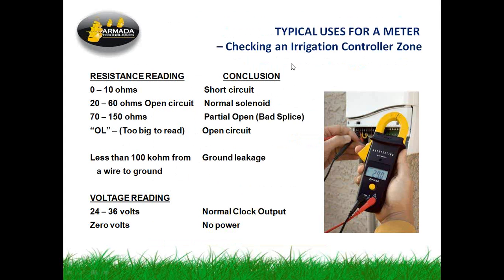To the next slide here, back to this thing about interpreting what the meter tells us. We have to make some real-world conclusions based on numbers coming out of the system. The resistance readings, for example, that are shown here have real-world meanings. If the resistance is very low and it's zero, you've got a short circuit. What we're interested in really is whether we've got a short circuit, an open circuit, or a normal solenoid, and we go in and read the resistance, and that resistance leads us to that conclusion. Same thing with voltages. I want to know if the voltage is normal. We're supplying power to the field. If it's reading 24 to 30 volts on the meter, that's what that means. I don't care almost what the number is. I just know that 24 to 30 volts is normal, and that means the clock's output is normal.